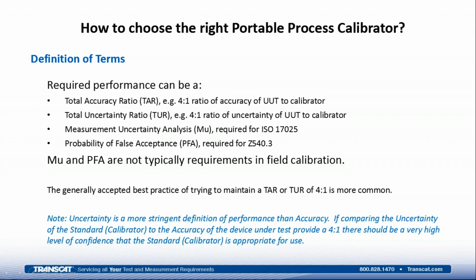So if we're comparing the uncertainty of a standard, a calibrator, to the accuracy of a device under test, and we still have a 4-to-1 ratio of the accuracy of the device to the uncertainty of the calibrator, then there should be a very high level of confidence that the standard is appropriate for use calibrating our measurement device.